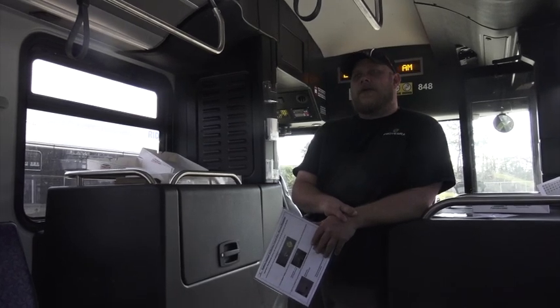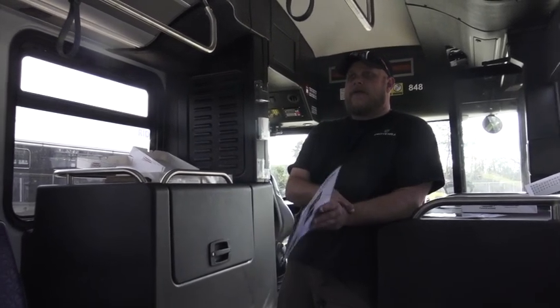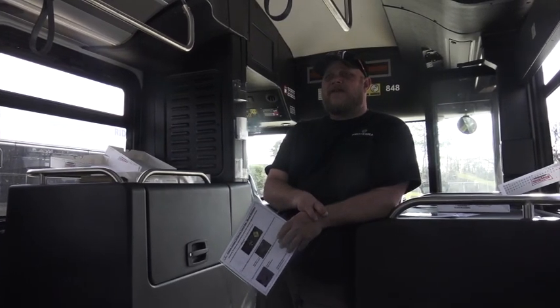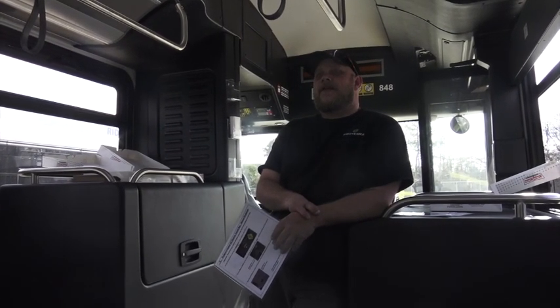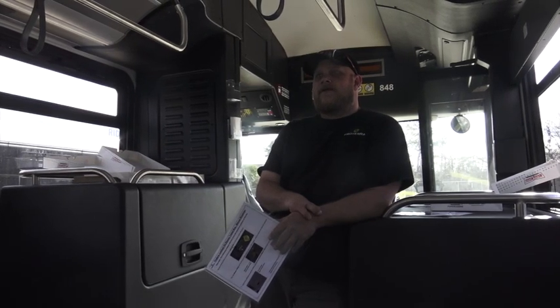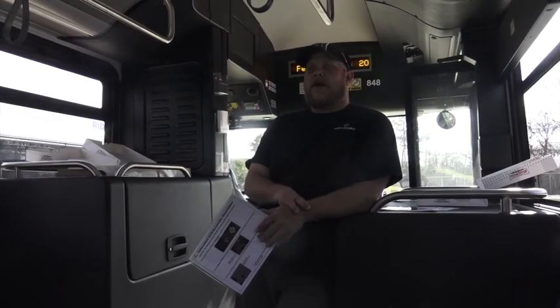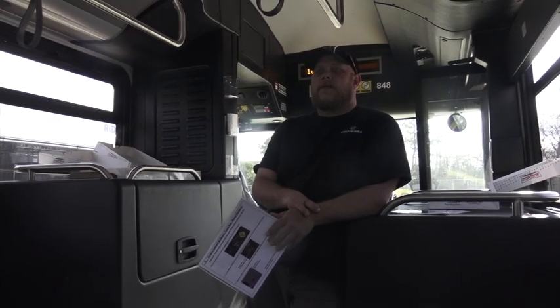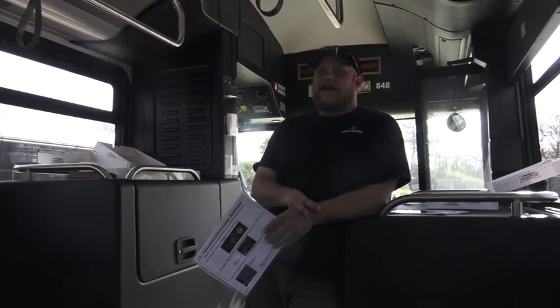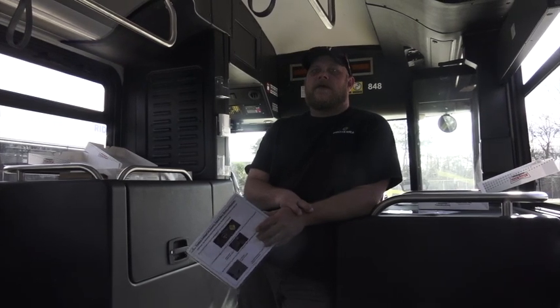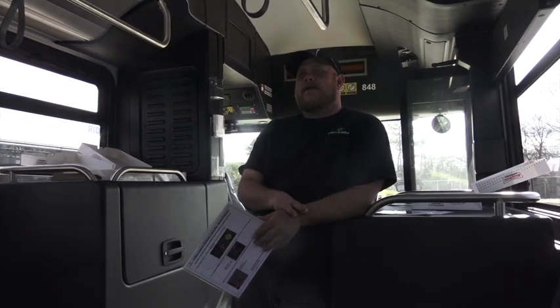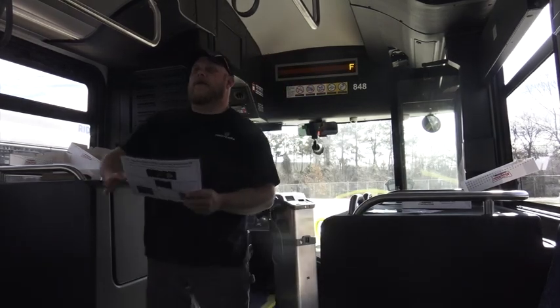The charger out there at the fast charger at the depot is a 500 kilowatt charger, so its max output is roughly around 500 volts at 1,000 amps. These here are 60 kilowatt chargers — they still run off of 480 grid voltage, and what we put out is a DC current, roughly around 200 amps at around the same voltage at max. These actually have the ability to pump out up to 800 volts, we just haven't gotten to that point yet.